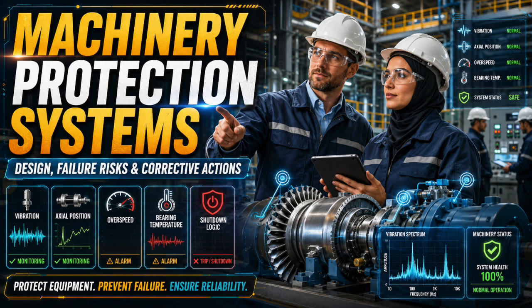Now let's talk about wiring, shielding, and grounding, because this is where good design often gets damaged in the field. A machinery protection signal is often small, sensitive, and exposed to a hostile environment. Heat, moisture, vibration, electromagnetic interference, radio frequency interference, ground loops, power cable coupling, poor shield termination, wrong conduit routing, water accumulation, bad junction boxes, loose connectors, cable damage.